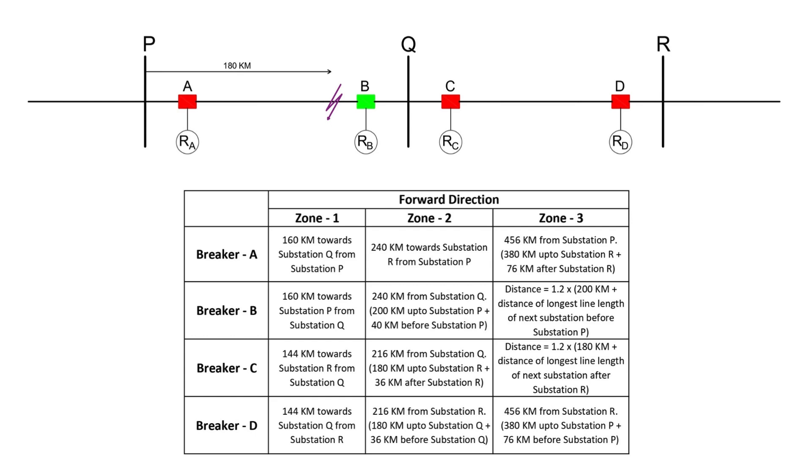If breaker B opens, the line will still be connected to substation P, meaning breaker A must trip too to fully isolate the fault. In this scenario, substation Q sends a direct trip signal to breaker A to ensure it trips immediately. If the direct trip signal fails, zone 2 protection of breaker A will activate as backup and trip the breaker after 350 milliseconds.